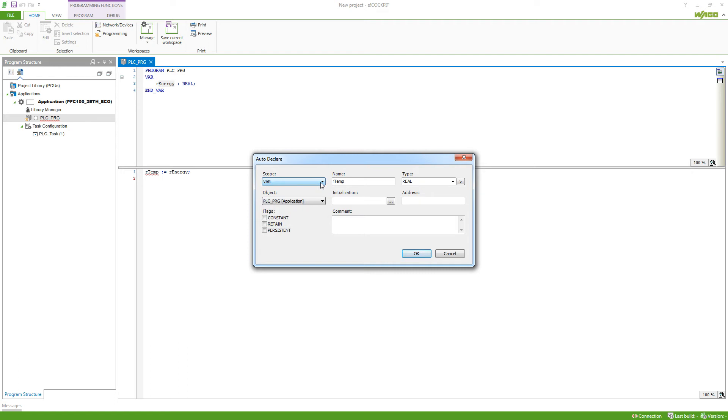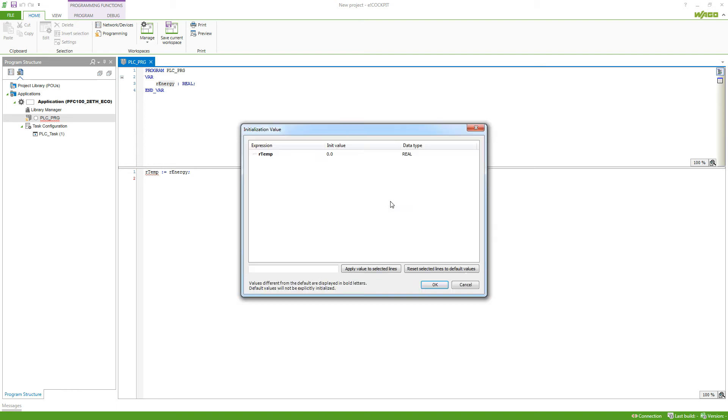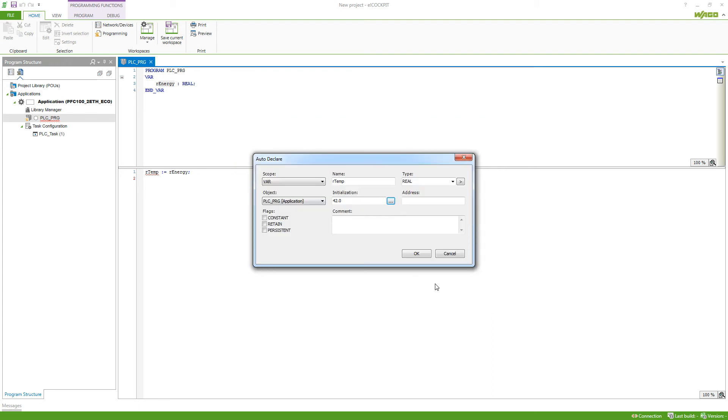Then we can declare an object. In this case, we just have the PLC PRG, so we can just choose this. But if we had others, we could also have another object where this variable is defined. Then we can initialize our variable. We can hit these three dots and then, for example, have the value 42 in here. Hit OK and then we would have the initialization of 42 for this variable. And an address, which is just rarely used now because unlike Codesys 2.3, flag variables are not automatically published via Modbus.